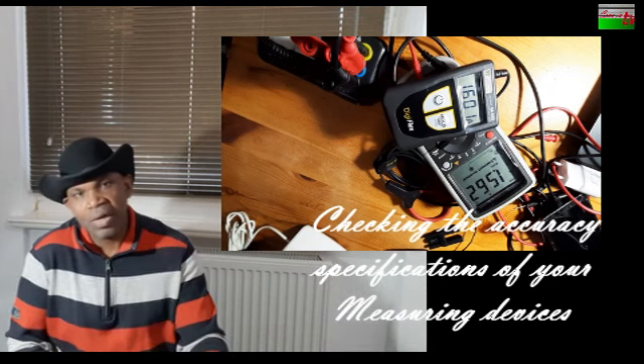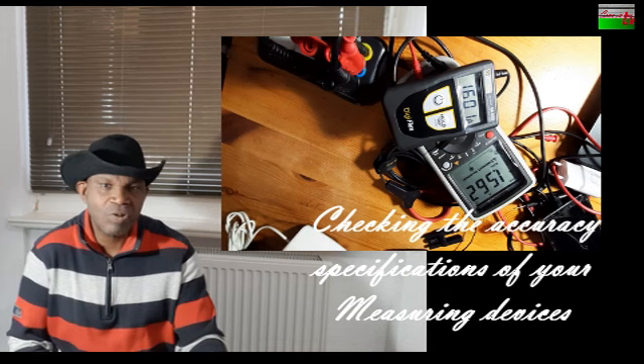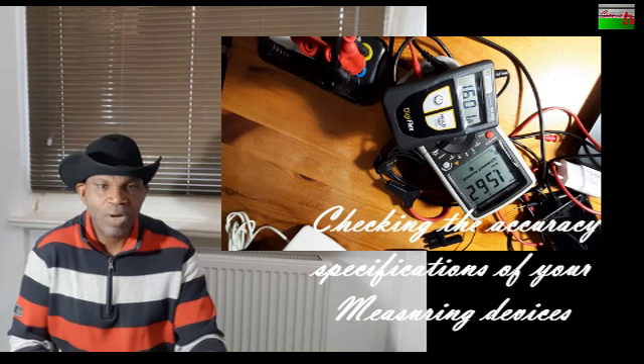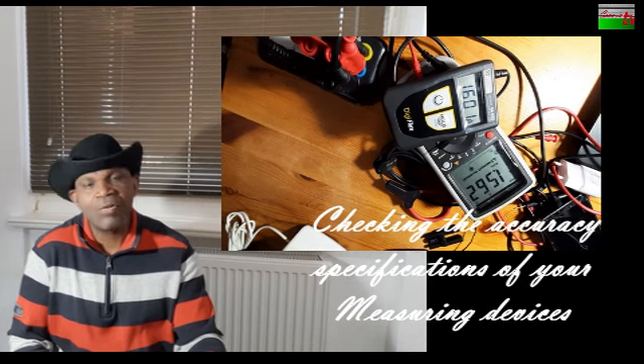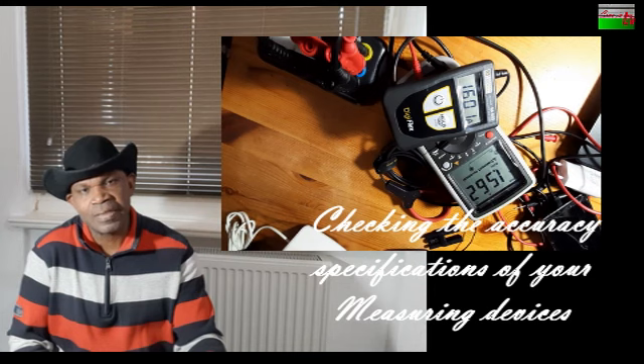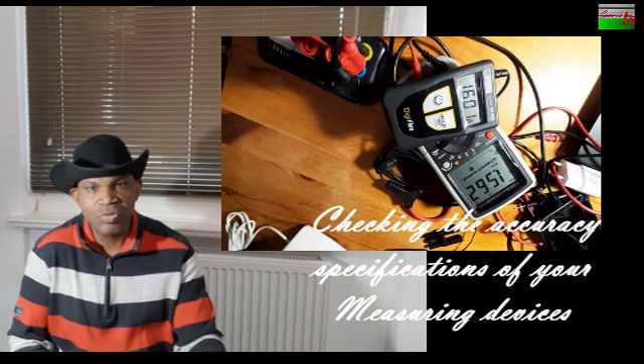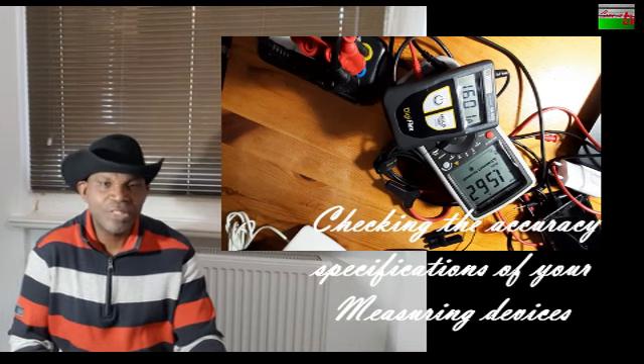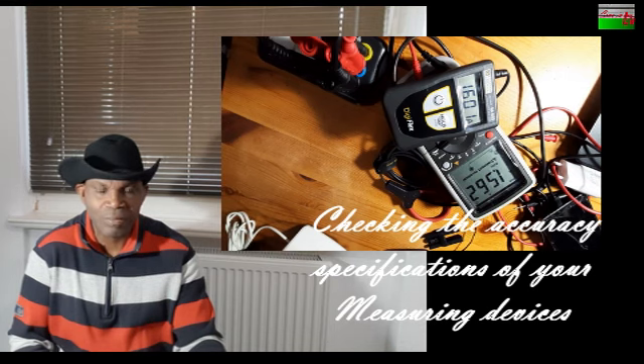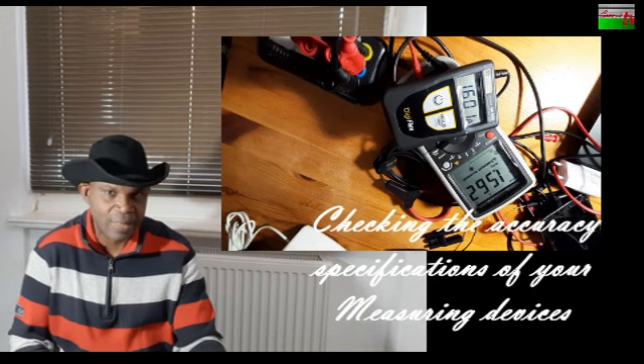The second way is what I shall be discussing in this video. All you need is to take the same measurements at the same time using 2 or 3 different equipments to verify the accuracy of your measuring device. If the other equipments used have precision values in the range of plus or minus 5%, the verified equipment is deemed to have correct measurements.